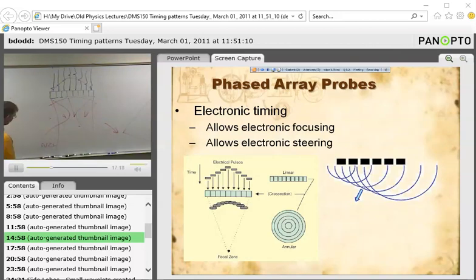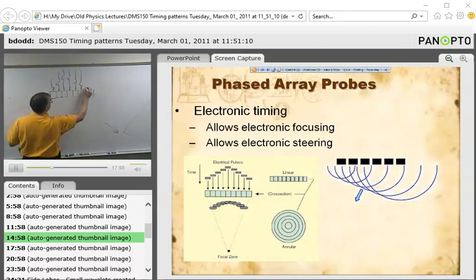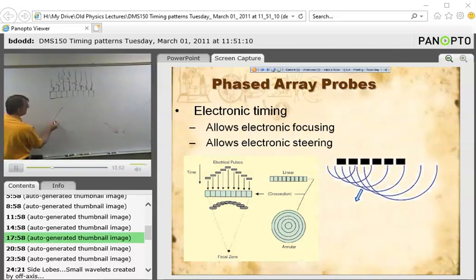All right, so what the manufacturers do is they take it one step farther and they actually will not only fire these off to steer the beam, but they will also focus it by firing them off in certain patterns, okay? So now I've got a beam that focuses, but it also kind of has an effect of driving the beam in this direction. All right, so we can change our timing pattern so that it steers it and focuses it at the same time, just kind of a combination of the two.